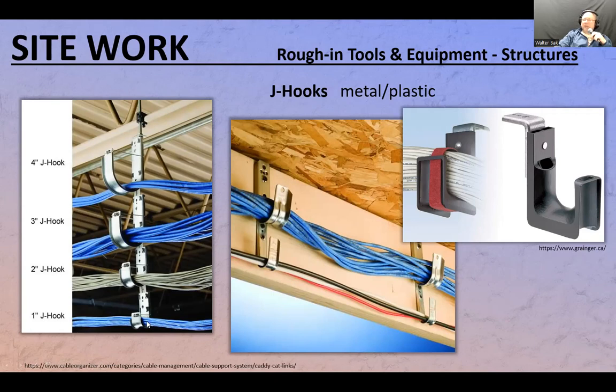And wherever there's companies, those distribution places that sell the J hooks, threaded rods, they will also sell all kinds of different paraphernalia to accommodate different situations that you're going to encounter. Sometimes you mount those threaded rods in the ceiling space, mounted to the ceiling, sometimes to the strut channel. Sometimes you have a T-bar. Why not use it? All right. So there's a metal construction in the ceiling when you pop the ceiling tiles.